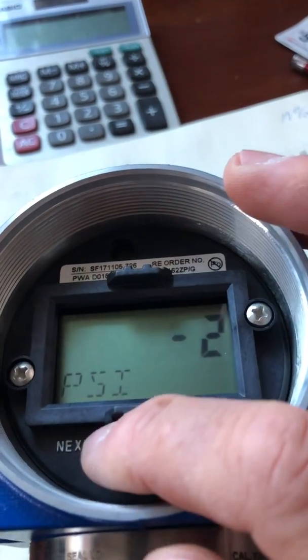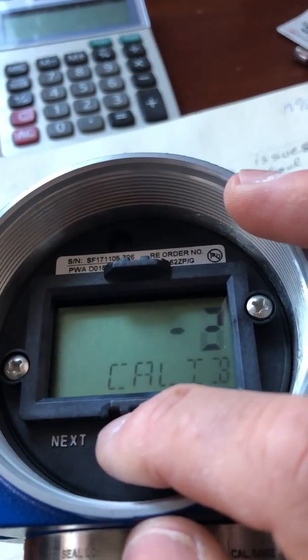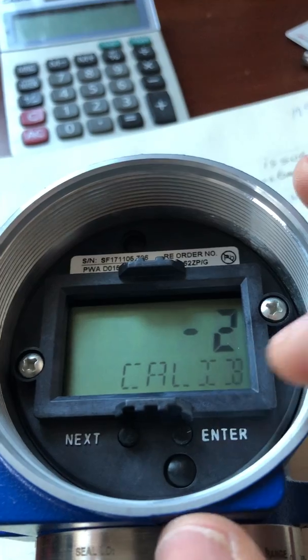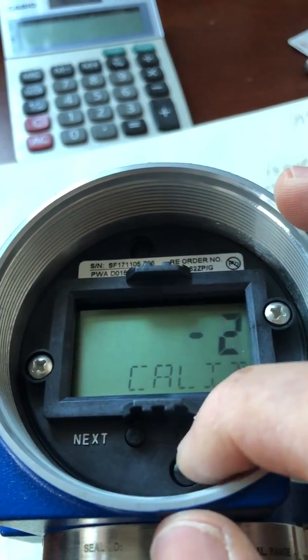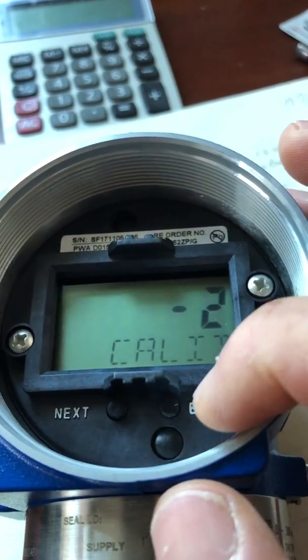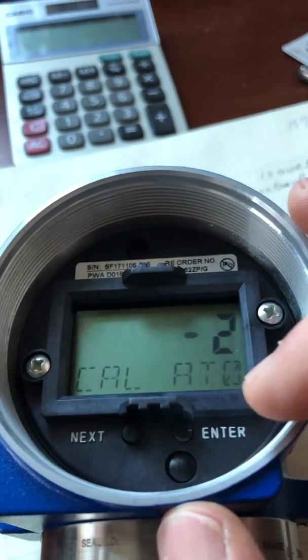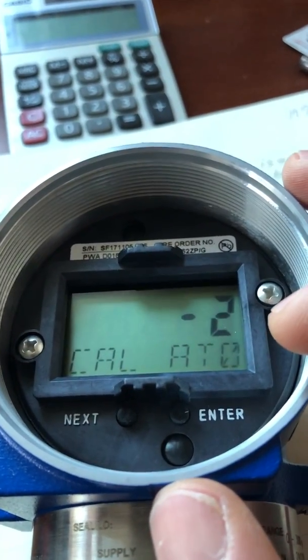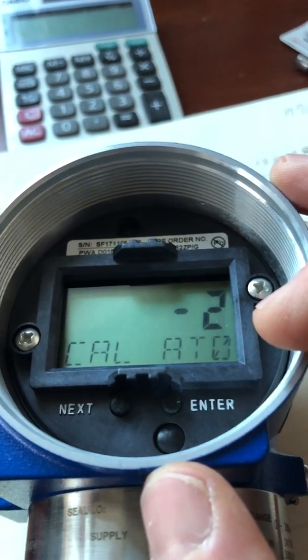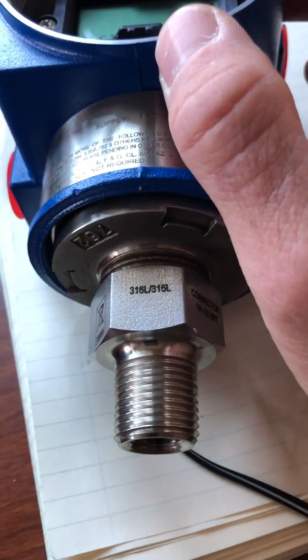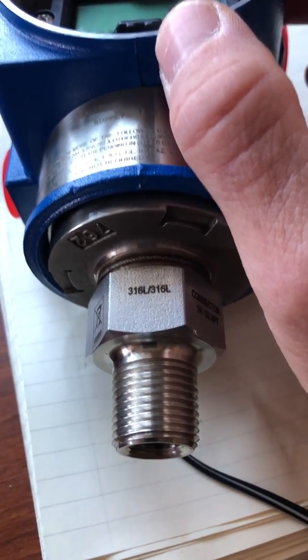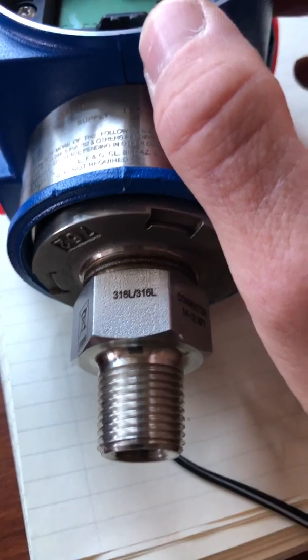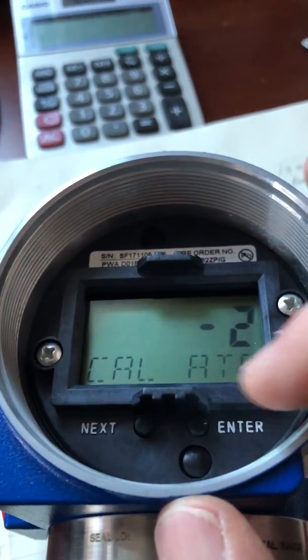In measurement mode, you just hit next to go into your menu. First one is calibrate, which is nice because that's the menu you wanna go into first. You go into it by hitting enter. And the first thing there is cal at zero. You can block it off with a valve and make sure it's zero if it's in service, or you can have it like this, at atmospheric pressure, and it is zero PSI, so you wanna enter.